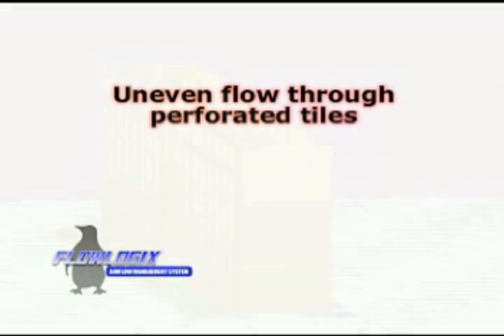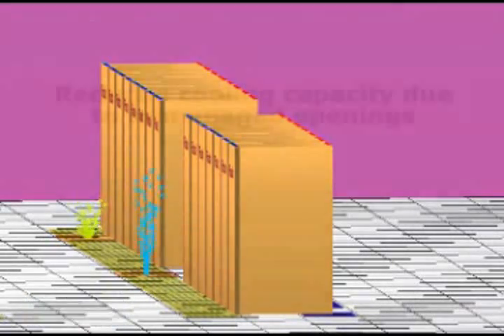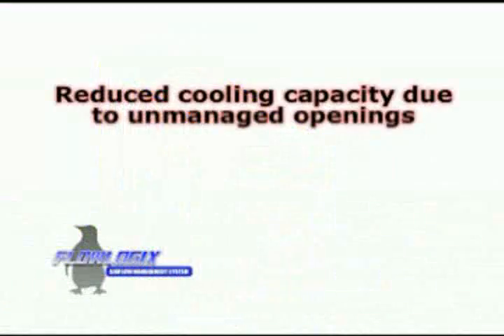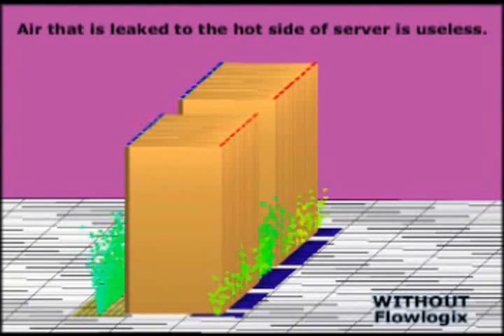Uneven flow through perforated tiles leads to hotspots within the room. This is due to an unbalanced air flow velocity and unbalanced pressure in the subfloor. Air flow leaked through unmanaged cutouts misses the heat load and is useless, greatly reducing cooling capacity as well as cooling efficiency.